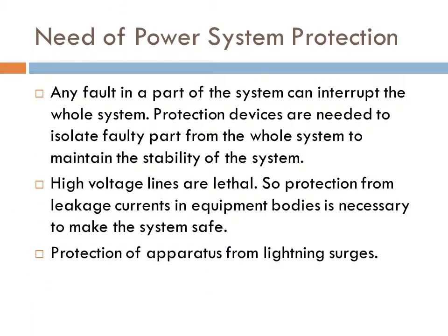First, the question arises why we need the protection of power system. Any fault in a part of system can interrupt the whole system. Protection devices are needed to isolate faulty part from the whole system to maintain the stability. High voltages in power system are lethal and can damage the equipment. So a proper system is required in order to save the power equipment. Protection of operators from lightning surges is also included in the power protection of power system.